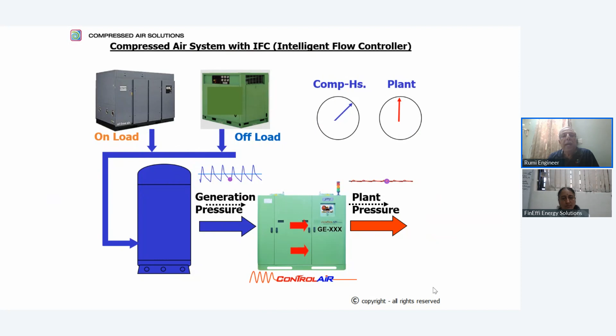We call it an intelligent flow controller device. You get a constant pressure - you are assured of the constant pressure. With that, we can switch off one compressor. Only 2 compressors are working - one will be modulating, one at the base load, one to do the peaking load. As per the demand, it will vary.